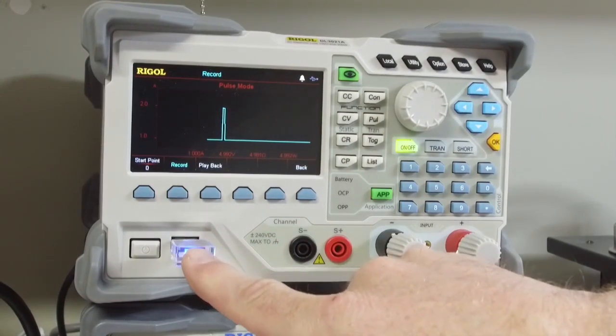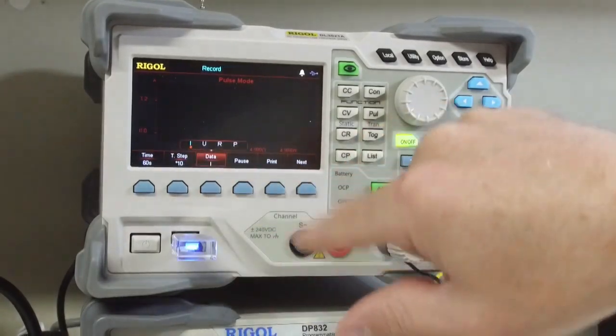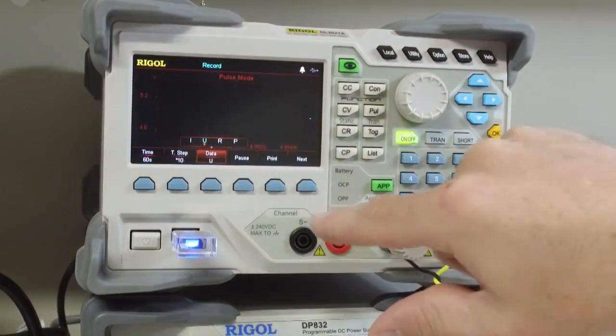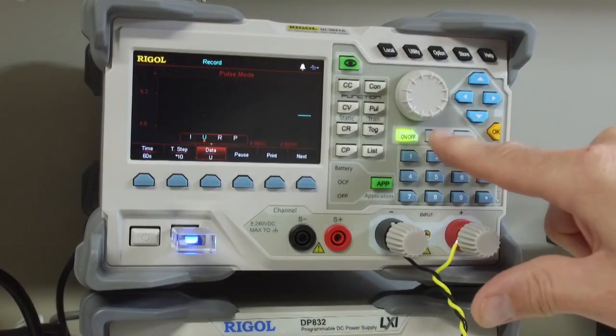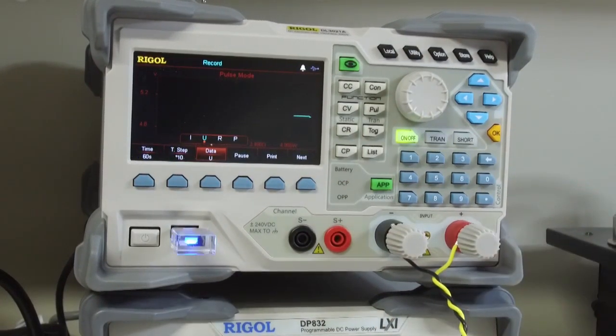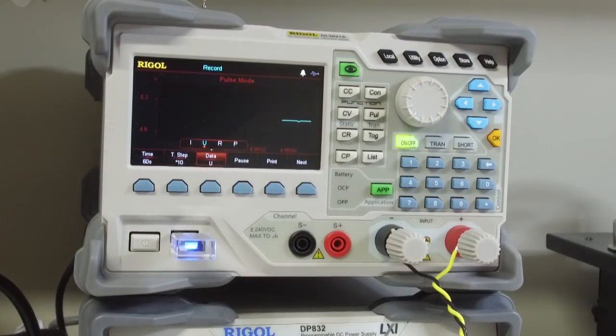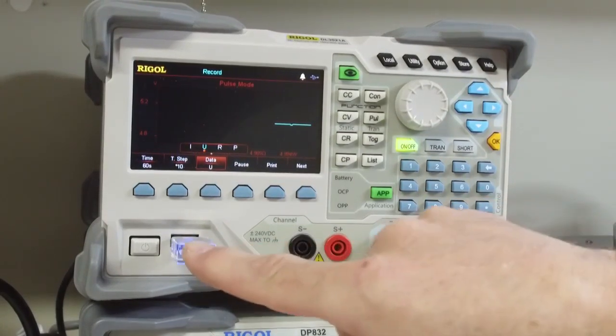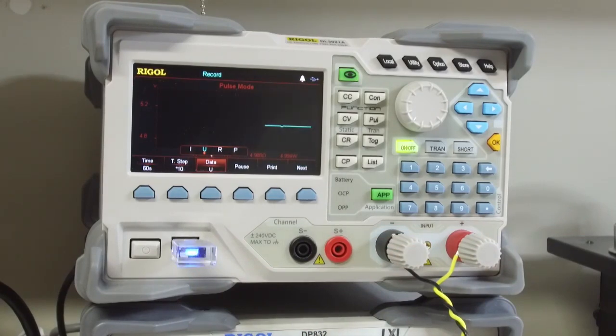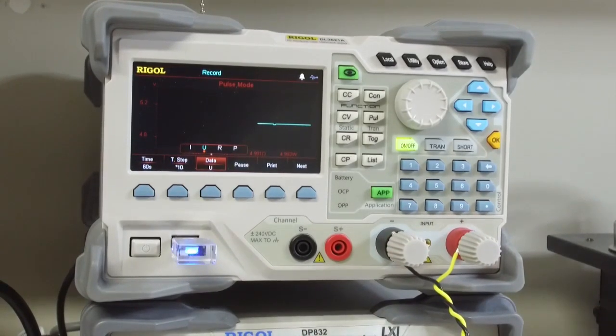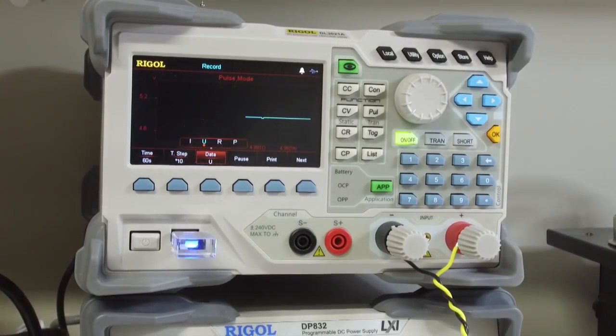You can see that this thumb drive is now blinking. We'll do that transient again. We can see the little teeny glitch there. And so it's kind of slick that it's recording data. And it's in like a comma delimited form, so you can easily pull it into a spreadsheet. And it's going to give you a time stamp, current, voltage.